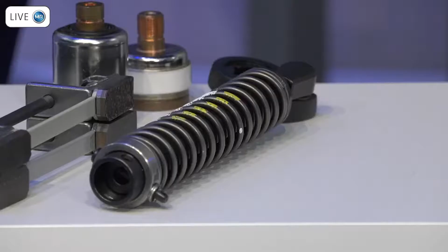Another example for an upgrade is the energy accumulator. We completely redesigned the energy accumulator. So the bottom plate is new, and the interesting thing is that we also redesigned the energy accumulator itself. When MR started to have the OILTAP V in the product portfolio, this was 1979, we delivered every OILTAP M with tension springs. This is the photo on the left. And since a few years, we have the energy accumulator with pressure spring design. I brought also one energy accumulator with me, which you can see on the front. So the blade is completely new, and the main part is the energy accumulator with the pressure spring design. The camera tries to zoom in so that you can also see that energy accumulator which I brought with me. I just turn it a little bit. This is the new pressure spring energy accumulator.